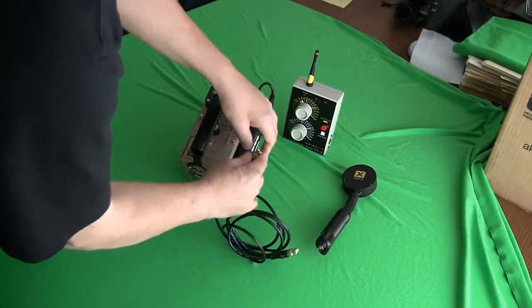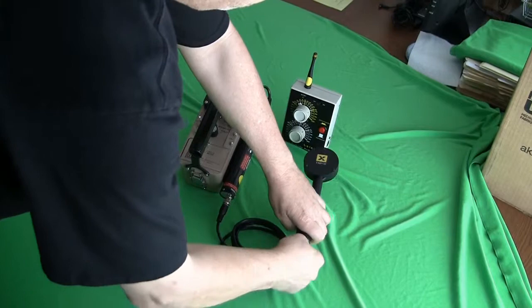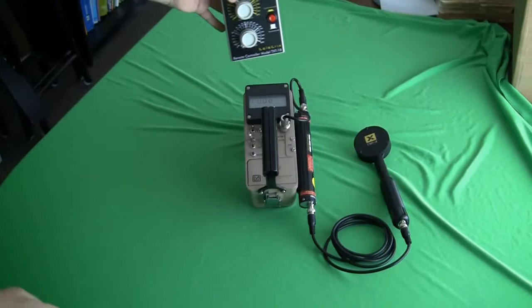Use a standard coax cable to connect any probe. In this case a pancake probe is used as a dummy prop. Energize the meter, which energizes the probe pack.